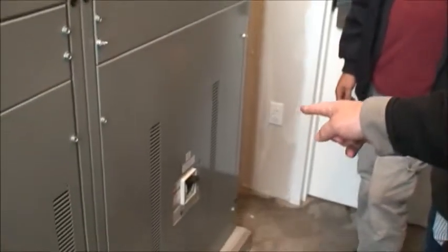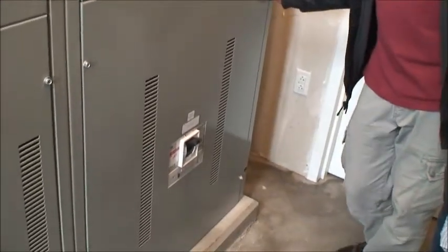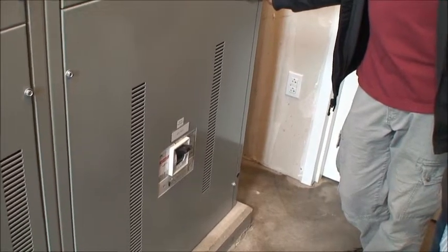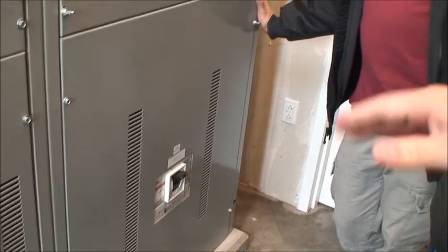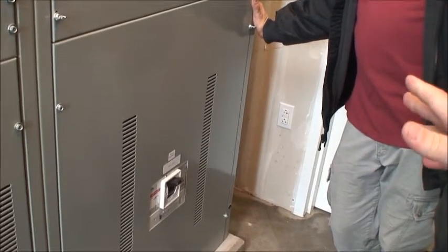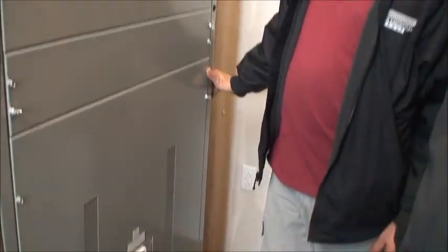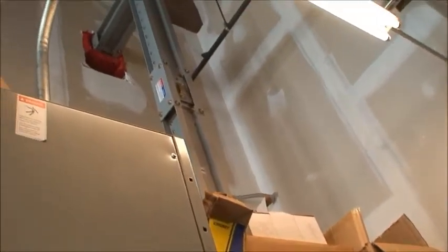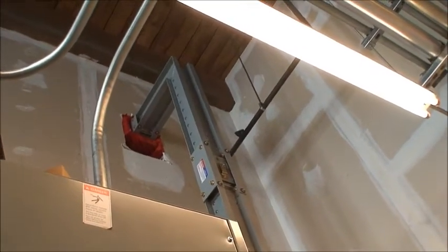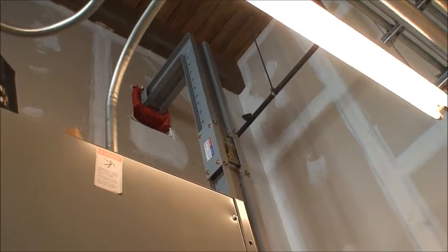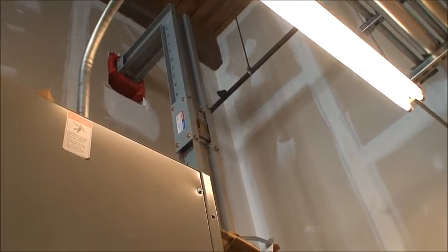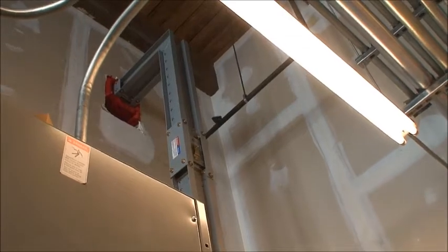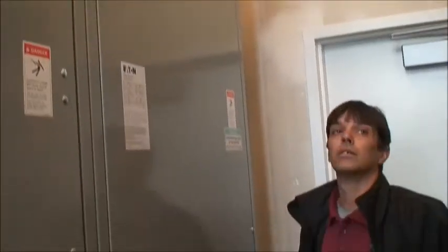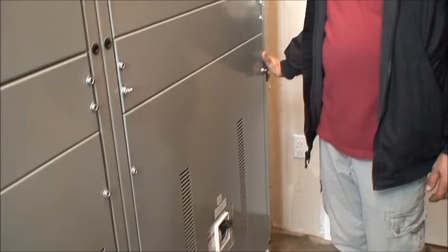Lastly, it's marked bus duct. This is the feeder to all of the apartment power. Obviously, we talked about the public being here. This is apartment power. We have an overhead bus duct, which runs up and goes across over to below where your meter sockets are. We'll go up to the floors and look at the individual meter sockets. But this is non-metered power going up to each riser so that we can have apartments that are fed from individual floors. That's why you don't have a bank.